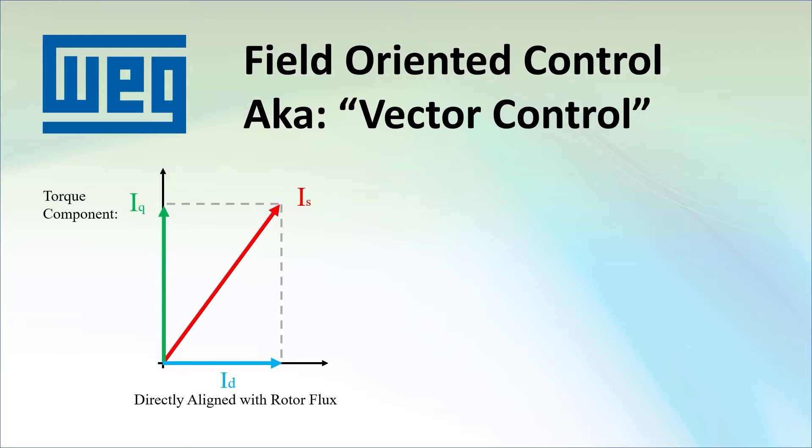So to change the torque, the drive's job is to keep those two vectors oriented at 90 degrees and just change the amplitude of the torque current vector, which is why we call it field oriented or vector control.